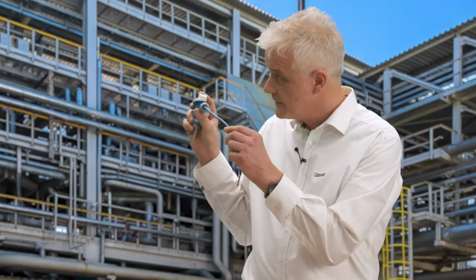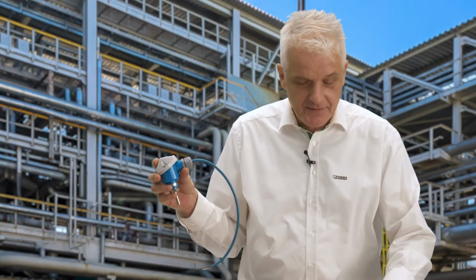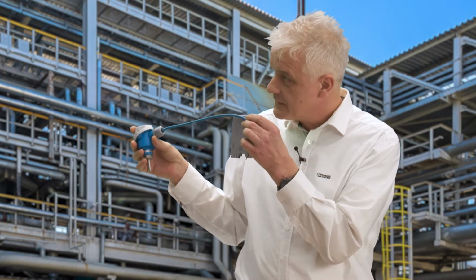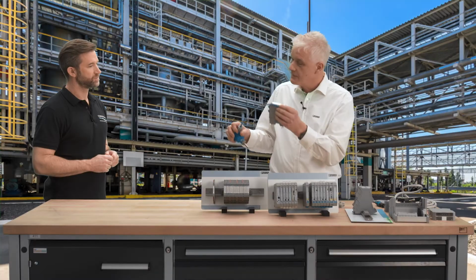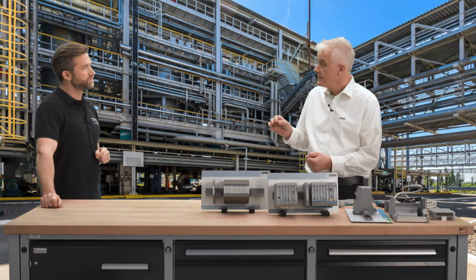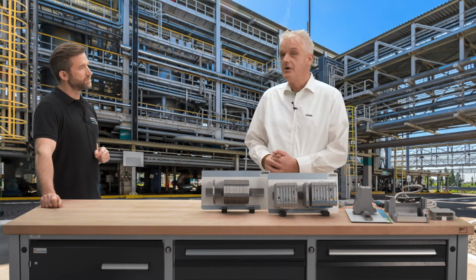That is, for example, the head transmitter, intrinsically safe, and that is an IS isolator, which is responsible to limit the energy safely which is let into the hazardous area. Signal conditioners with Ex i inputs or outputs, also known as IS isolators or isolated IS barriers, are associated equipment and thus a central component of the Ex i type of protection and must be used unless the I/O cards have Ex i inputs or outputs.